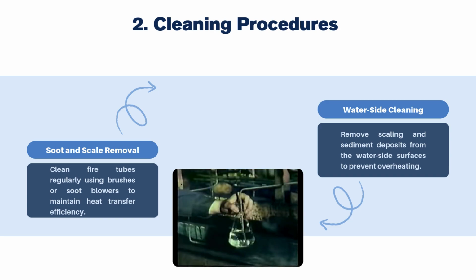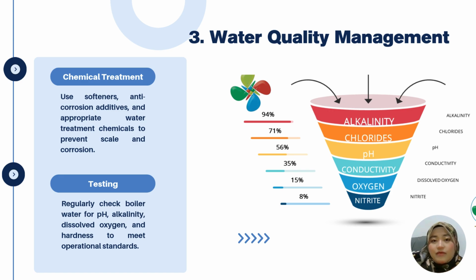Okay, next we have water quality management. This procedure involves chemical treatment and testing. Chemical treatment can be said to be using softeners, anti-corrosion additives, and appropriate water treatment chemicals to prevent scale and corrosion. Second, testing revolves around regularly checking the boiler water for pH, alkalinity, dissolved oxygen, and hardness to meet operational standards.